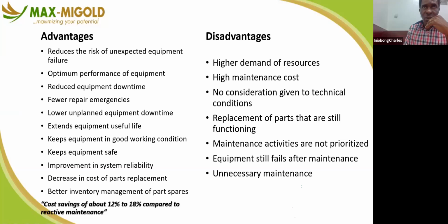Sometimes you go to change the oil of a generator and you see that the oil can still be used, can still have another 200 hours run. But because you have put a schedule around it, and there's a vendor managing that contract, you can't tell the person not to change the oil, maybe to take it home, sell it, refine it, and reuse it. You must stick to it because that is the plan. Okay?